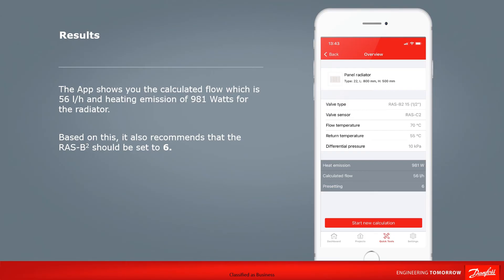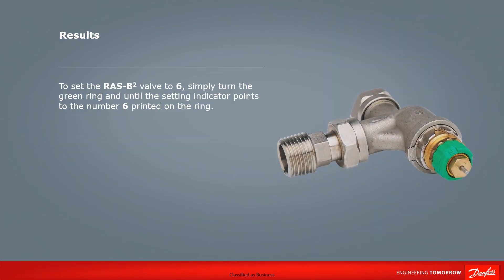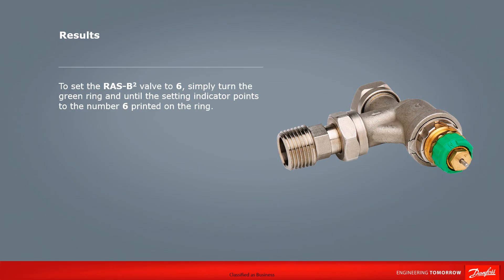Here you can see the app provides a recap of the details entered, as well as information on the heat emission and flow as calculated to ensure a return temperature to the boiler of 55 degrees C. It also recommends that the RAS B2 valve be set to 6. To set the RAS B2 to 6, simply turn the green ring until the setting indicator points to 6 on the green ring.